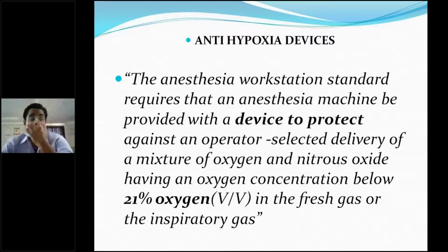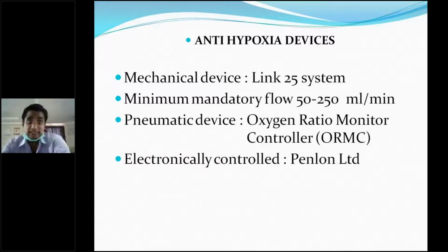As I have told you, we have some important safety devices. Here we have the anti-hypoxia devices. One is the mechanical device, that is the Link-25 system. The other one is MMF, known as minimum mandatory flow. The other one is ORMC, oxygen ratio monitor controller.